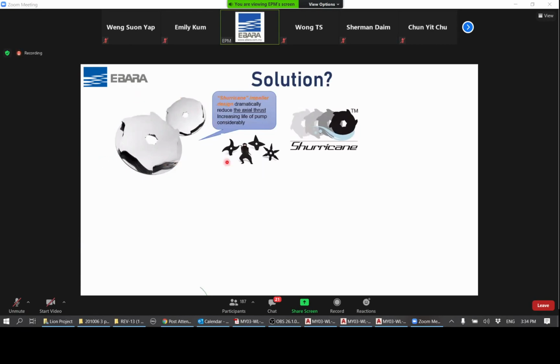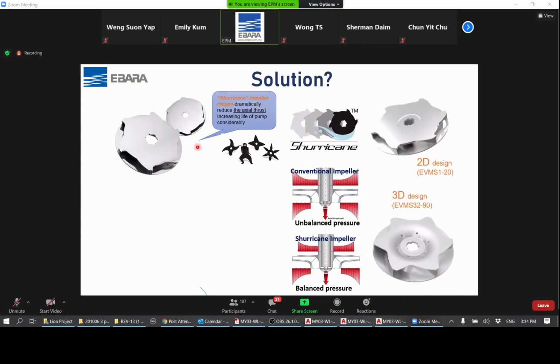Okay, you might have to relook into it. The design of the impellers has been shaped to dramatically reduce the axial thrust, which is caused by the pressure imbalance between the top and bottom. Now, how is that achieved? On the commercial side, if you can see from here, in the earlier picture, a conventional impeller will have this. Actually, everybody has it.